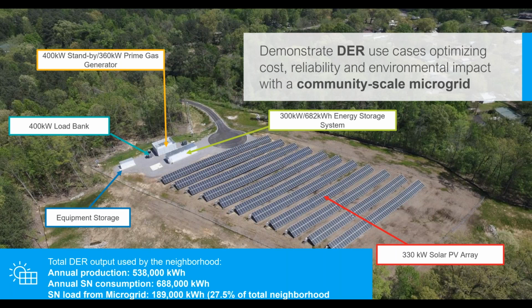Now, how did we design the microgrid? Looking at the functionality and then the capacity in this case, we have a 330 kilowatt solar PV array. We designed an energy storage system with 300 kilowatts and 682 kilowatt hours, and a generator that has about 400 kilowatt standby and 360 kilowatt prime capacity. And for research purposes, we have a 400 kilowatt load bank.